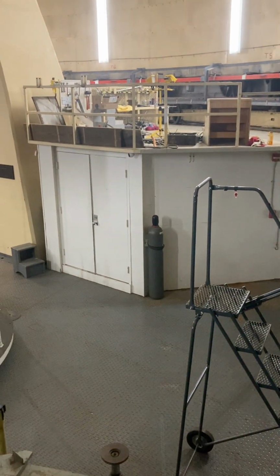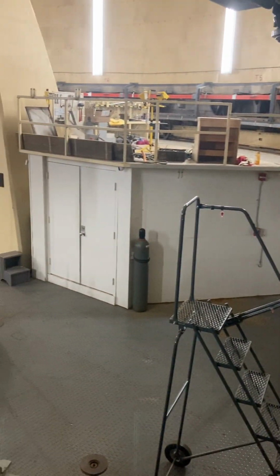The last thing to do is re-enable the dome e-stop system. When we were dissecting the old contactor box from the dome, we discovered this black mystery wire. This is the e-stop wire. It has a dedicated slip ring connection to the magnetic contactor in the old control room.